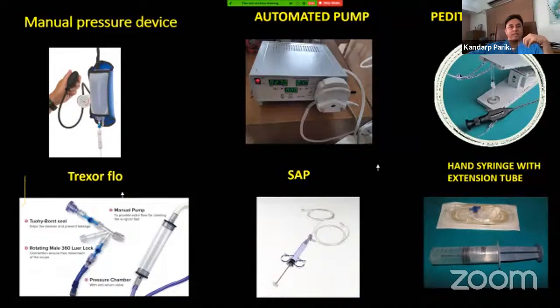Normally, we recommend gravity irrigation, where we connect the IV set with the pint and with intermittent pressure with the syringe. Some people use a manual pressure device like this. Please do not use this. This will increase intrapelvic pressure significantly. Sometimes the pressure goes above 300. So don't use it. An automatic pressure pump you can also use, but there is no control on the pressure.